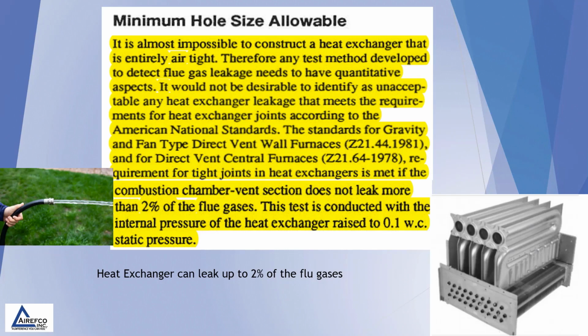This is a statement from a natural gas appliance testing facility which states that it's almost impossible to construct a heat exchanger that is entirely airtight. Many technicians have found this to be true when they try to fill the heat exchanger with water, and they find that a heat exchanger will leak quite a bit of water out of it because it is not completely sealed. The agencies that certify gas furnace appliances have an acceptable leak rate of 2% of the flue gas. This test is conducted with the internal pressure of the heat exchanger raised to 0.1 inches of water column static pressure.